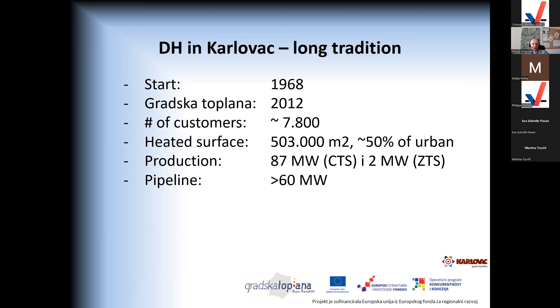About 300 customers are business ones. We heat around 500,000 square meters of heated surface, which represents around half of the urban part of the city. Our production facility consists of 2 active boilers with a combined power of 87 megawatts for central district heating, plus a smaller unit across a couple of buildings with 2 megawatts power, mostly driven with natural gas. Our pipeline has a capacity of more than 60 megawatts and is 21 kilometers long. We have 176 indirect-type substations, plus 9 substations on this small closed system.